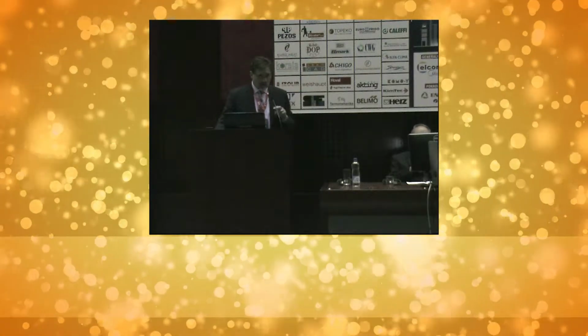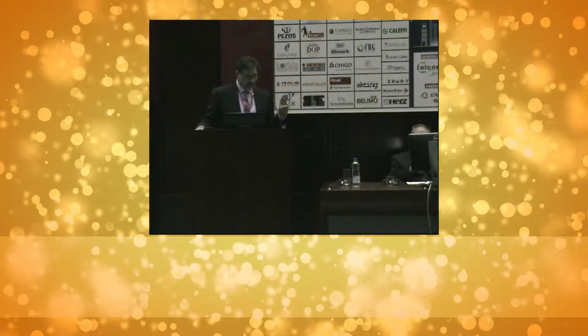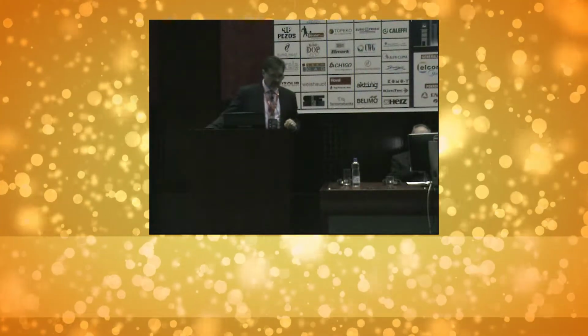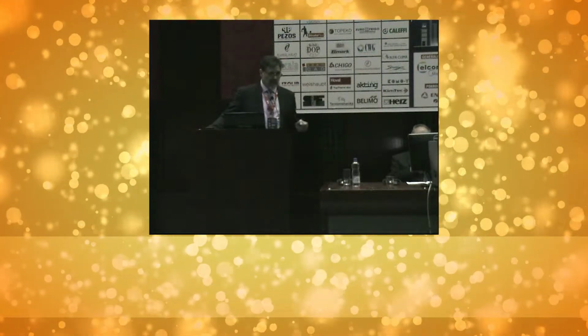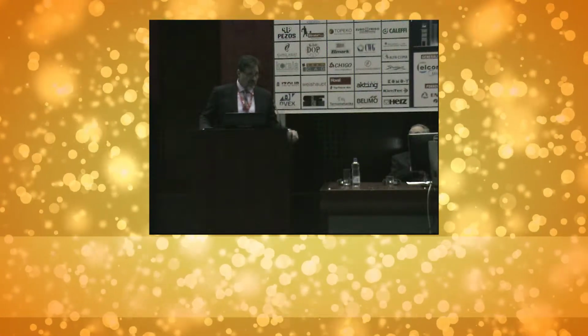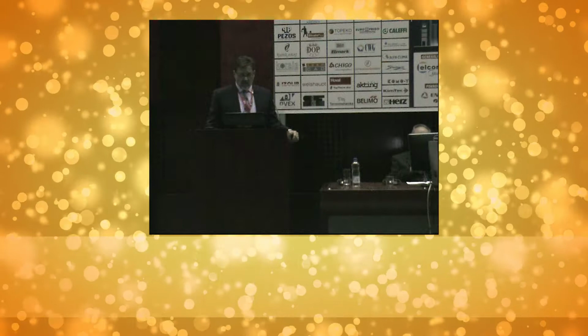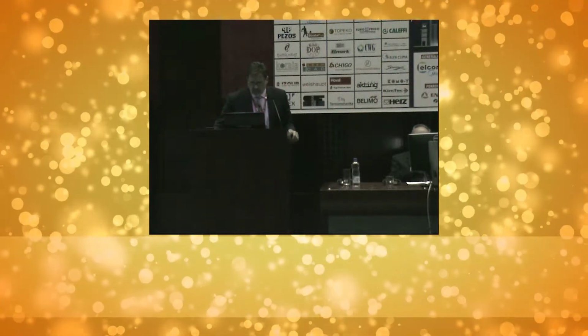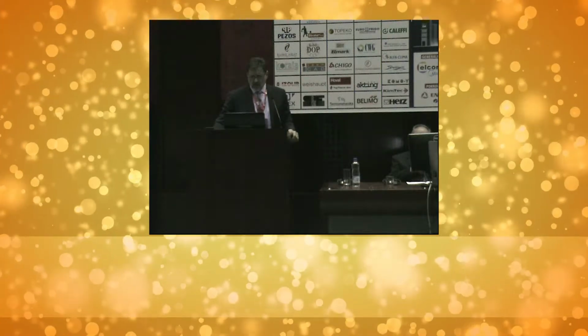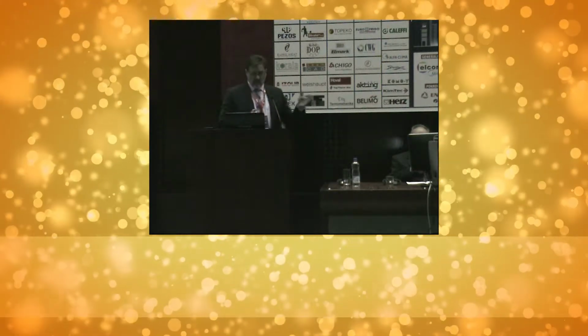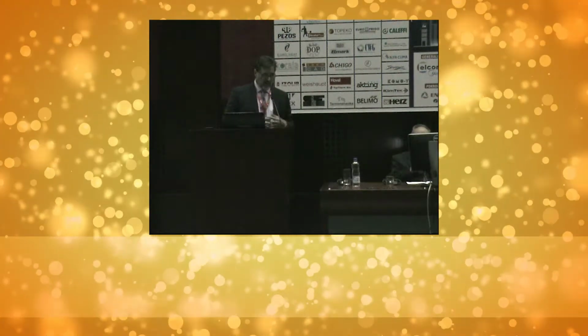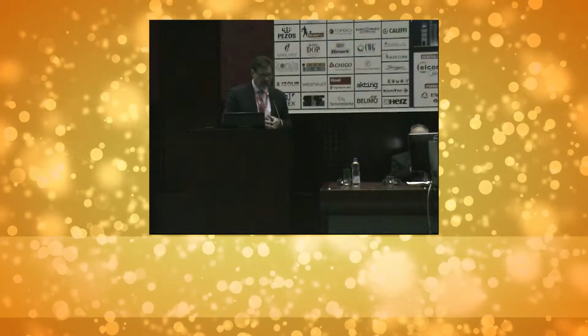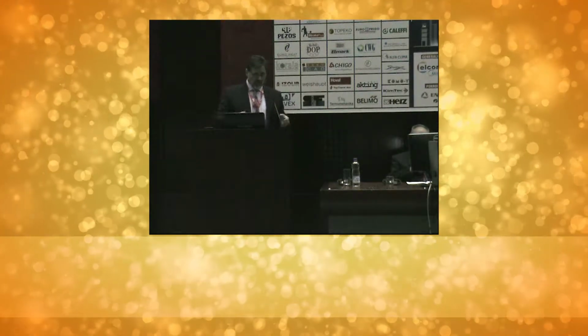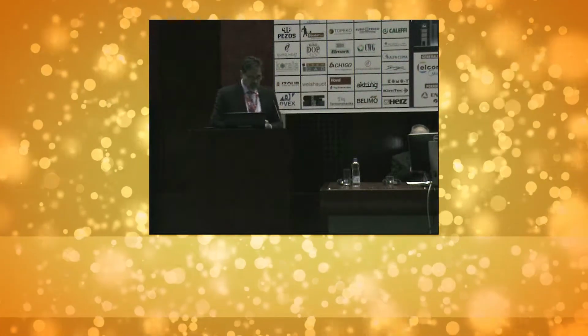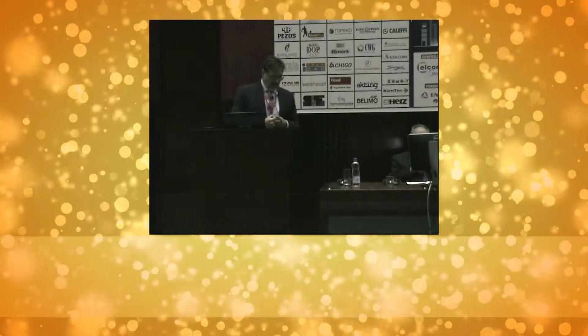If we base it on that, we find there are only 2 particular sensors in industry that we use. One is the classic velocity pressure sensor that works with the pressure drop, and the other one, which is the key of this, is the thermal dispersion. On the slide, the velocity pressure sensors are on the left, and you can see all these pipes. There's nothing to it, it's just the pressure drop. Everybody's familiar with that. The bigger the pressure drop, the more accuracy you get. The problem is that bigger pressure drops will get you more acoustics and more fan energy.